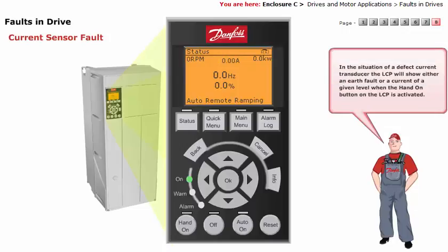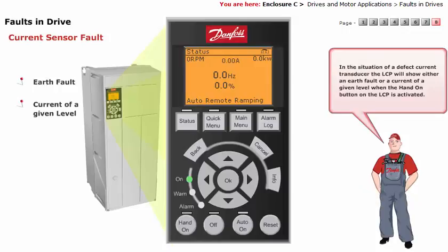In the situation of a defective current transducer, the LCP will show either an earth fault or a current of a given level when the Hand-On button on the LCP is activated.